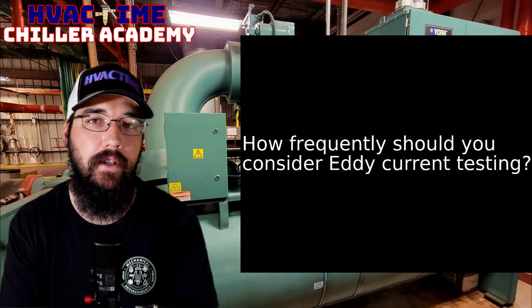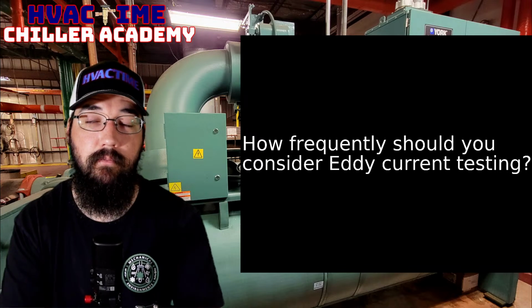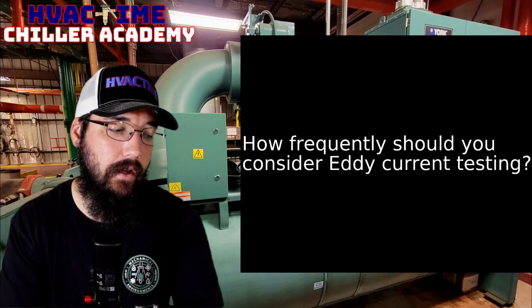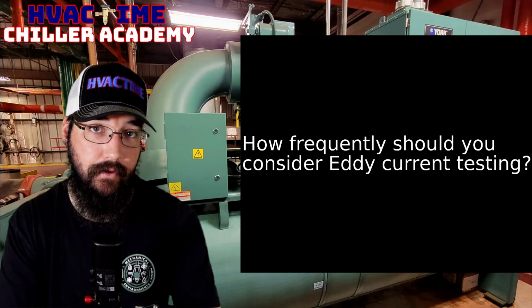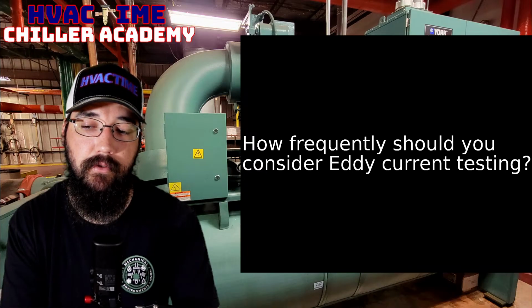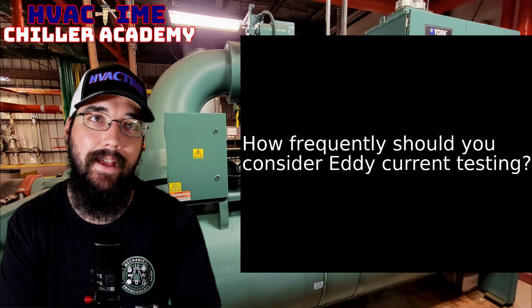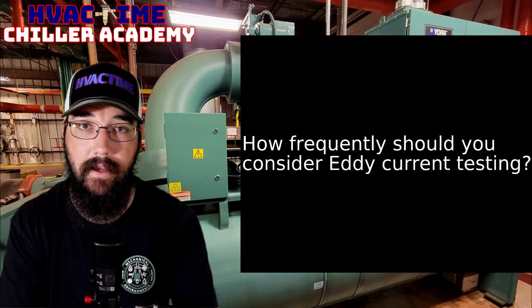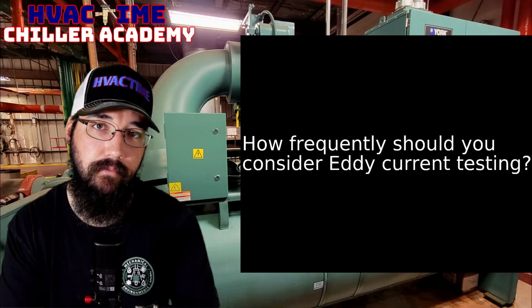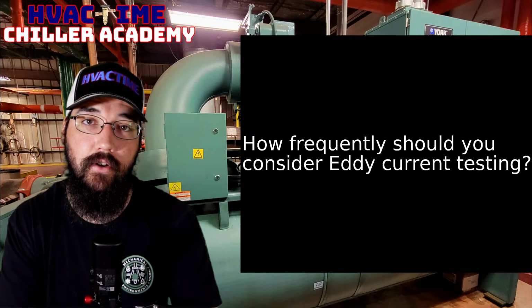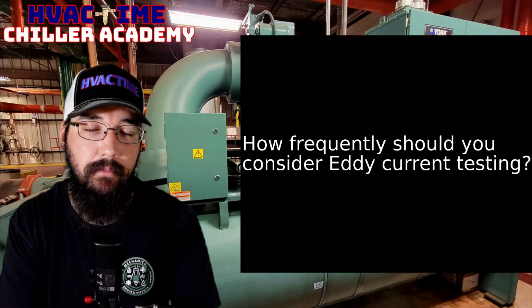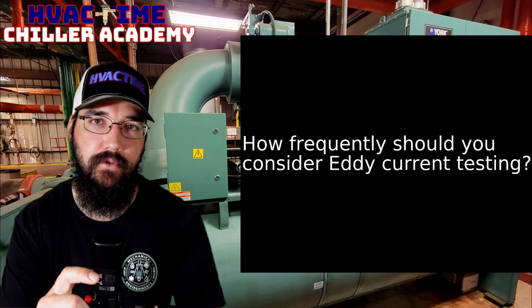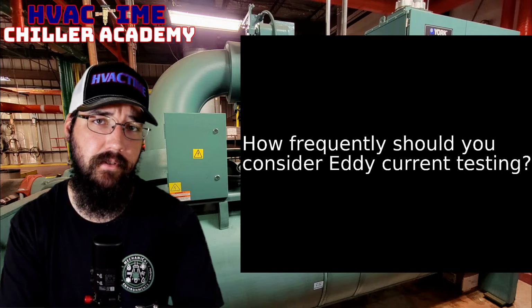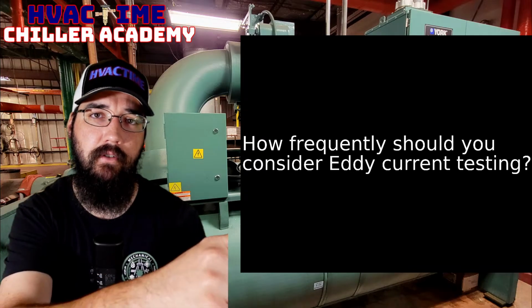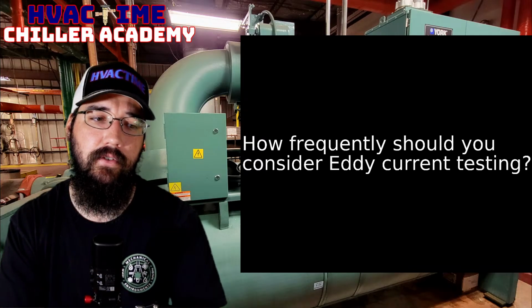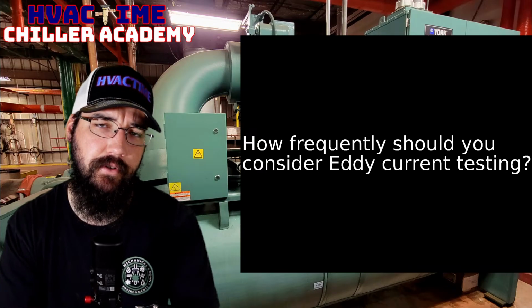Excluding external events, of course. Another one that happened was at a really old plant: the pump strainers just disintegrated, came apart, and turned into shrapnel down the piping. That got into the chiller condensers and was wreaking havoc. That's another opportunity where you'd say, let's go ahead and eddy current these and see what we find, because all those little shards of strainer running through the loop become puncture points as they bounce around inside the tubes.